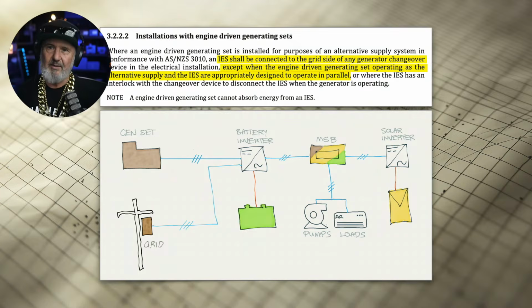So I'm just going to use brand names here. For instance, Selectronic can take a generator as a source, parallel their inverter with it, and as this little picture shows, provide a solar inverter as another source all at the same time. And they can even switch between grid and generating set. So they can have a contactor that can switch between grid and generating set. So when the grid fails, you've got a backup generator and you've got a solar inverter, but they have a reverse power protection feature, so no solar power or battery energy can flow back to the generating set.